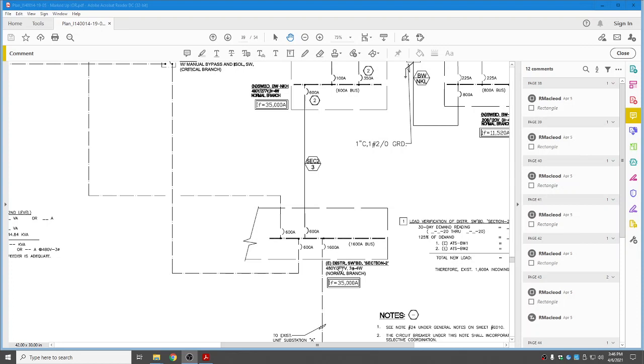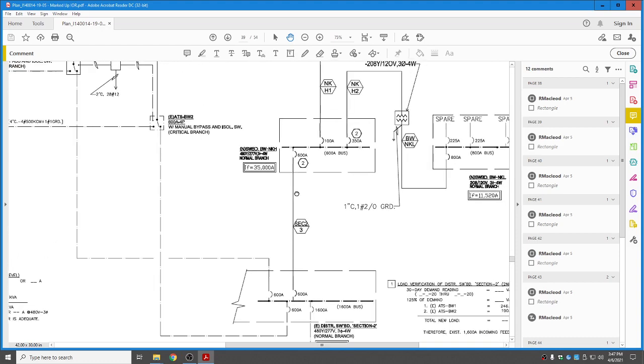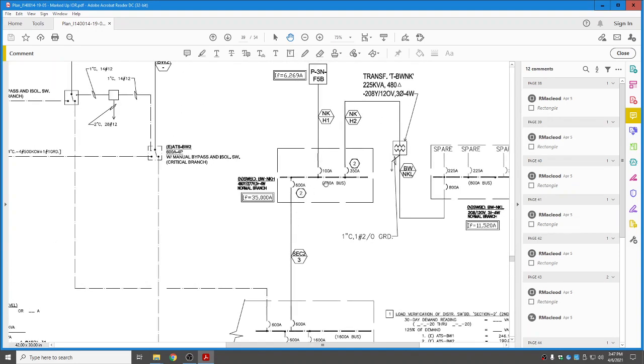But let me see if I can walk you through this. The distribution switchboard, okay, this is 480, 277 volt, 3-phase, 4-wire, normal branch power. Okay, now we have a 600 amp or 1600 amp bus here, and coming off it we're going to have two 600 amp breakers, right? Coming off this switchboard, going up, we're going to go to another switchboard with a 600 amp bus, normal power. Up here we're going to have a 100 amp and a 350 amp breaker.